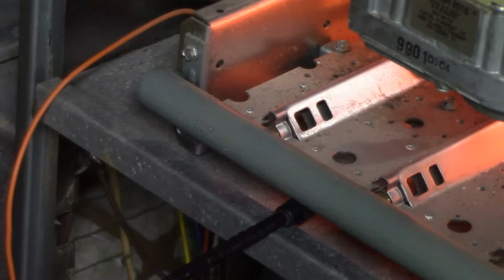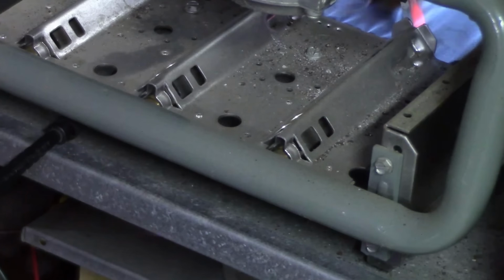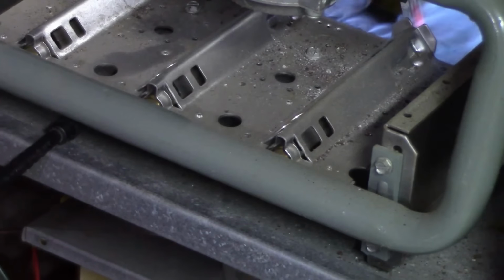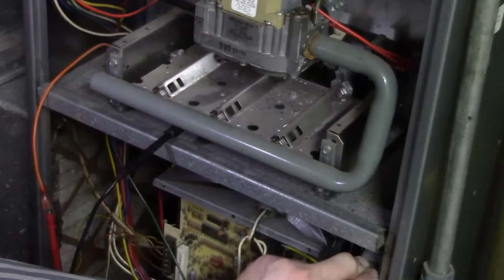This flame sensor is picking up a really good reading. Key thing is you want to wait until the blower motor kicks on, all the electronics, everything like that. I've seen them drop out. Blower has clicked, we're on. 3 microamps DC, very well. Nice blue flame right there. Everybody can kind of see it. Maybe. How's that? Yay, right? So, this one doesn't need cleaning. We're going to do it anyway.